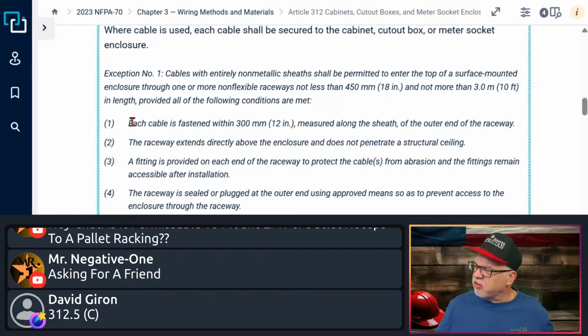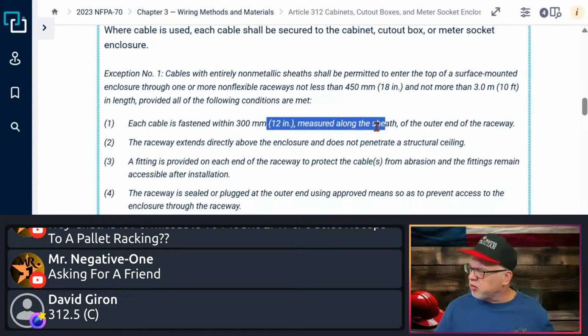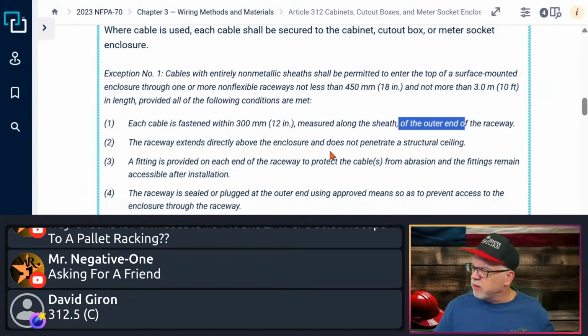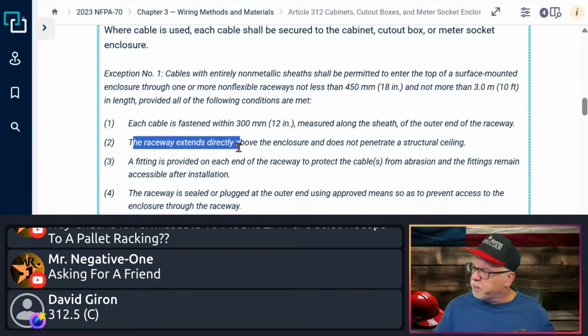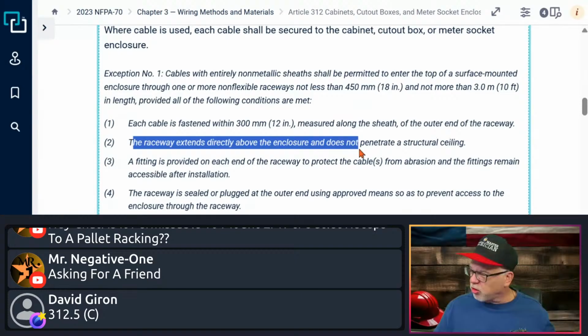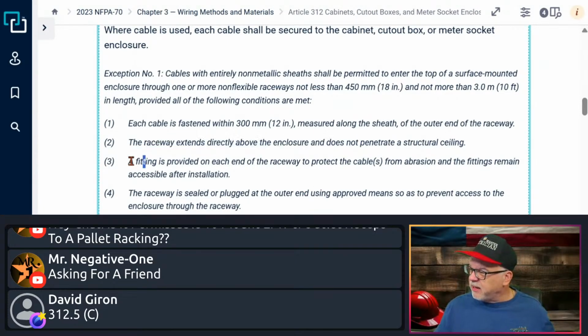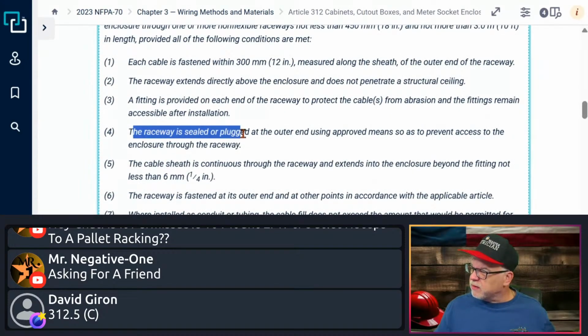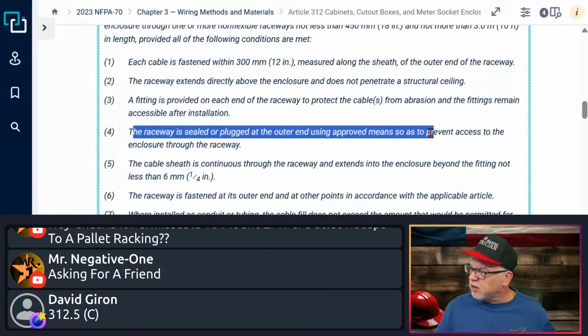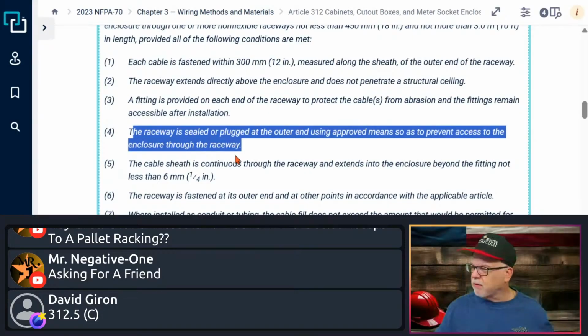All right? Now, each cable that enters is fastened within 12 inches, measured along the sheathing, not just measured, it's along the sheathing, okay, of the outer edge of the raceway. The raceway extends directly above the enclosure. It does not penetrate a structural ceiling, okay. A fitting is provided on each end of the raceway to protect the cables from abrasion, and the fitting remains accessible after the installation. Hard to do that in the wall, coming in the back, by the way. Next, the raceway is sealed or plugged at the outer end using approved means so as to prevent access to the enclosure through the raceway. Fill it, okay? A lot of times they do that.